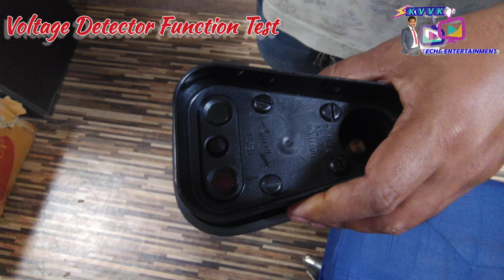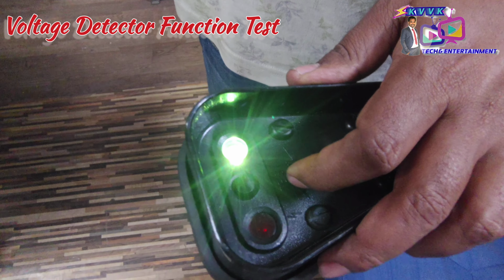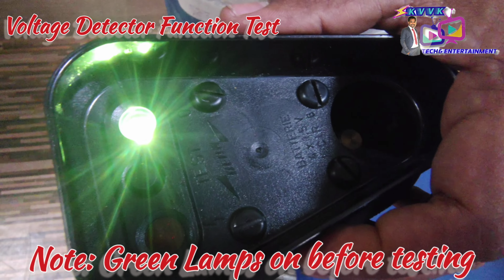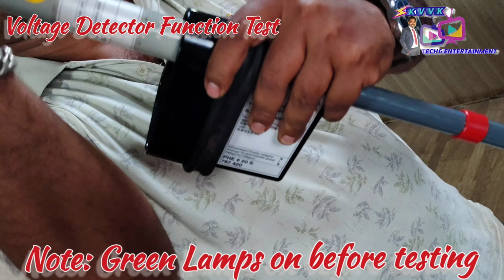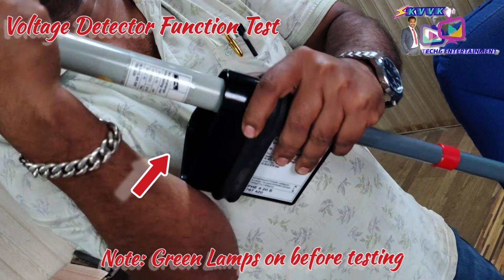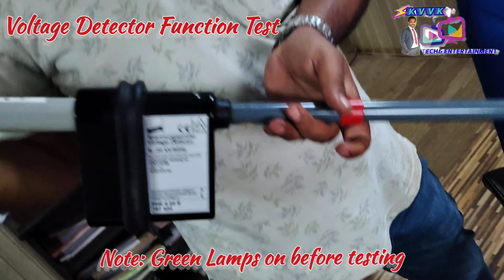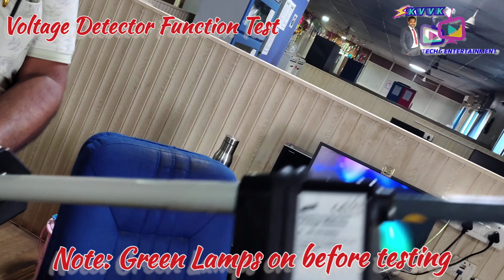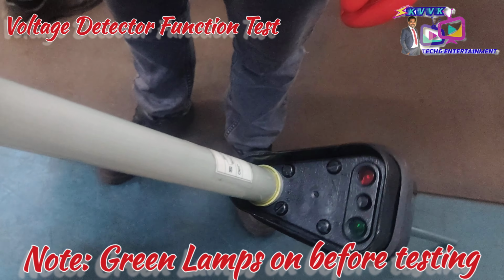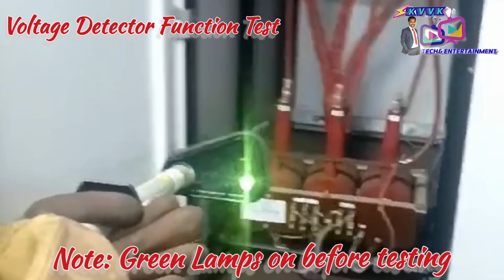Before the detector can be used for further tests, the test button must be pressed again and the function test performed. Now we can connect the insulated handle to the indicator. Please note that testing for safe isolation can only be carried out as long as the green indication lights on. The equipment automatically switches off after 40 to 60 seconds.